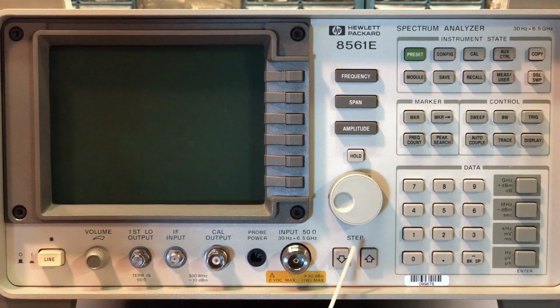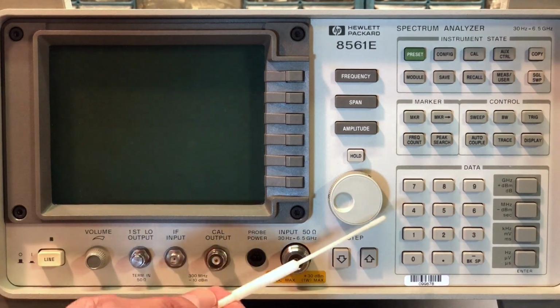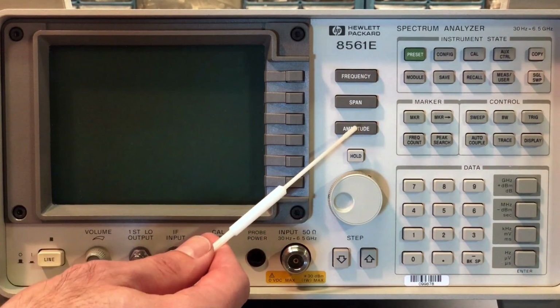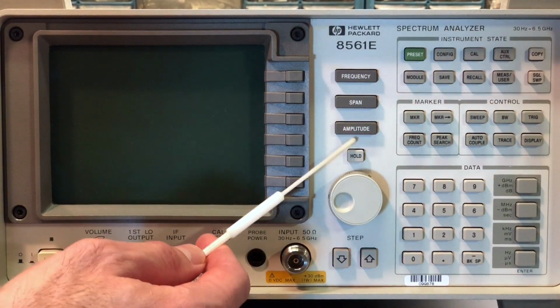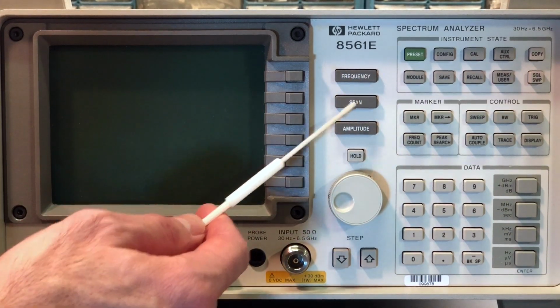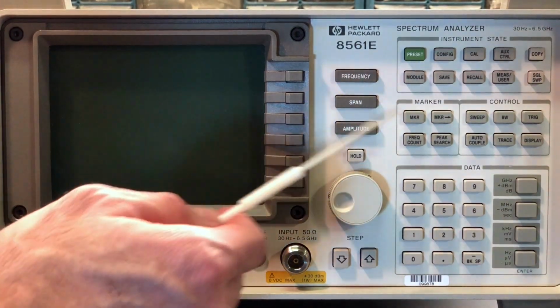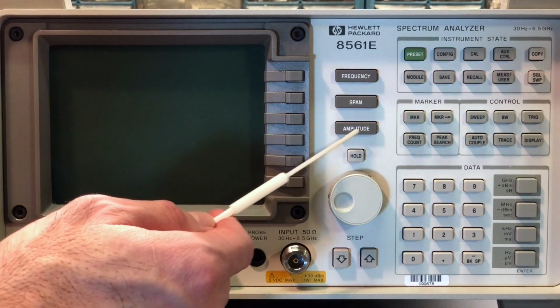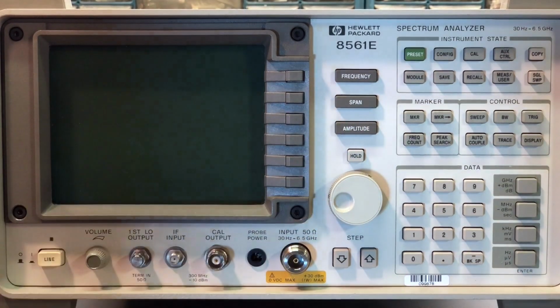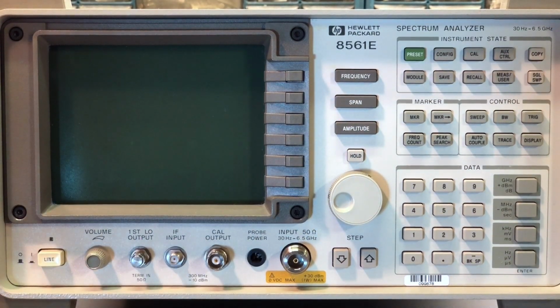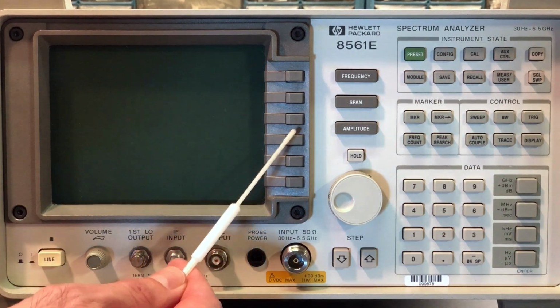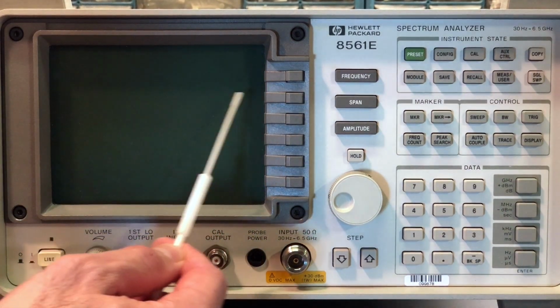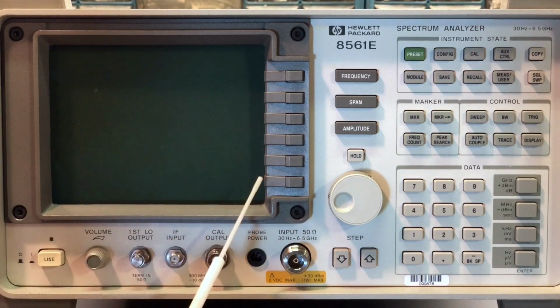Now over here, the step up and down and then this knob are just used to move through numeric values and settings. So pretty self-explanatory on that. The frequency span and amplitude are some of the main settings that you'll often use. These buttons get used a lot right here. So setting the frequency span, and then of course the amplitude on the display. I'll demonstrate those when I put a signal into the instrument. You'll see those in use. These buttons right here are for the soft key menus. So there are indications on the cathode ray tube over here on the display.